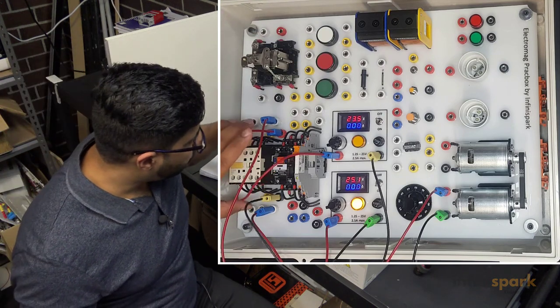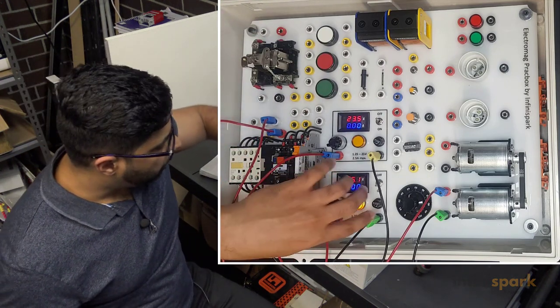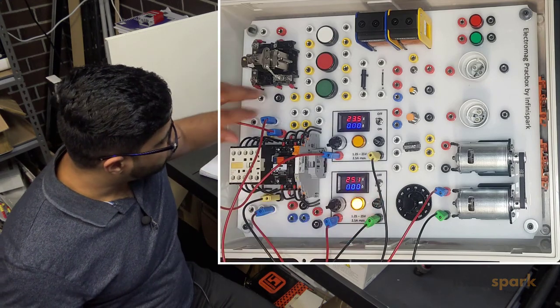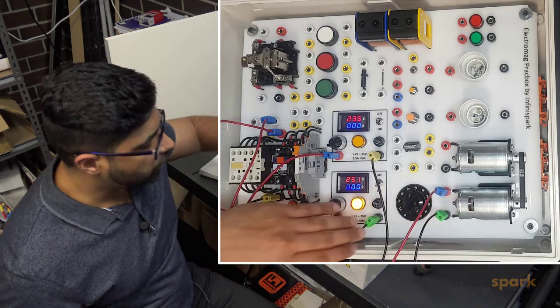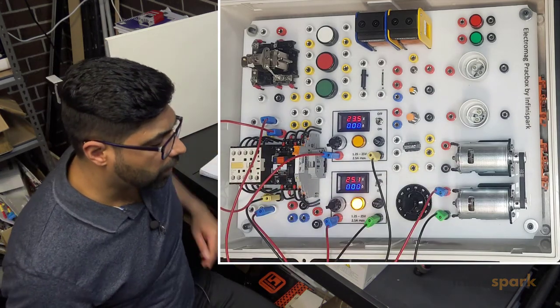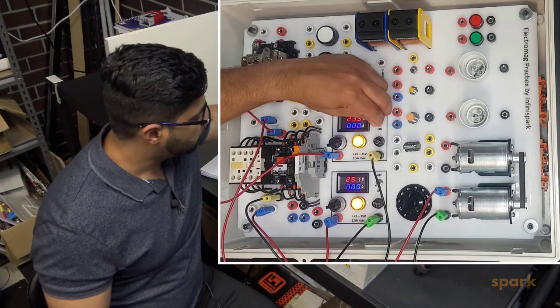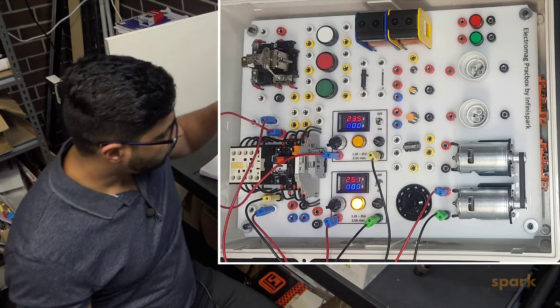As soon as the contactor coil is powered up, the power through this power circuit goes to this contact here and comes out to this motor and finishes the circuit that powers our motor. Let's do it again.